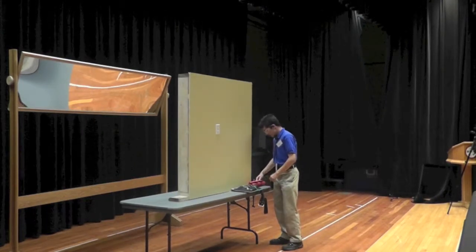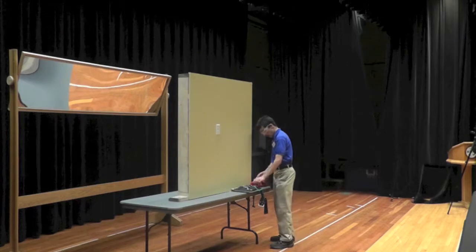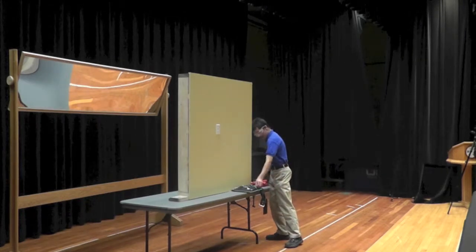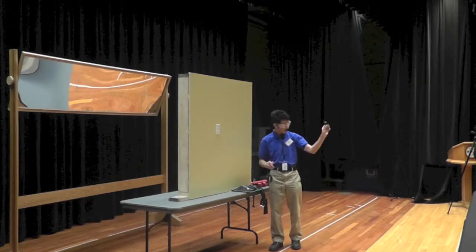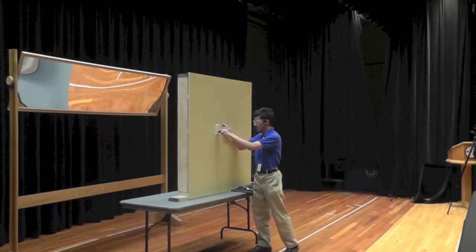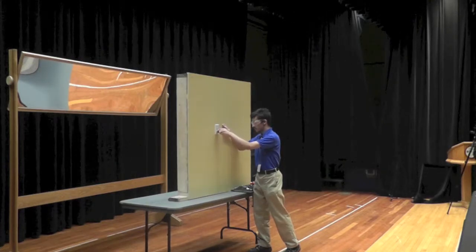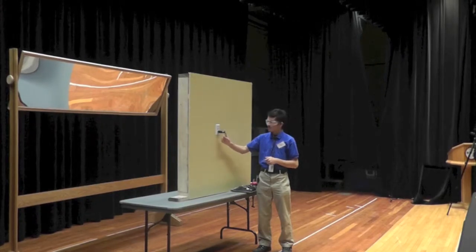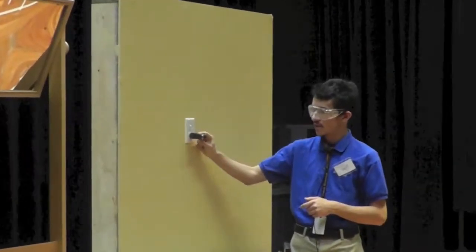To test this, we will use a plug-in tester manufactured by Greenlee. We plug it into the receptacle, and as you can see, the three lights have not turned on. This means the receptacle is de-energized.